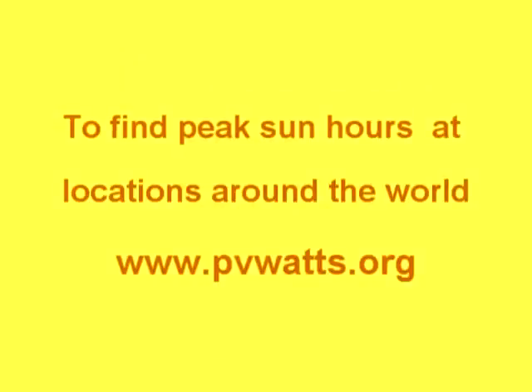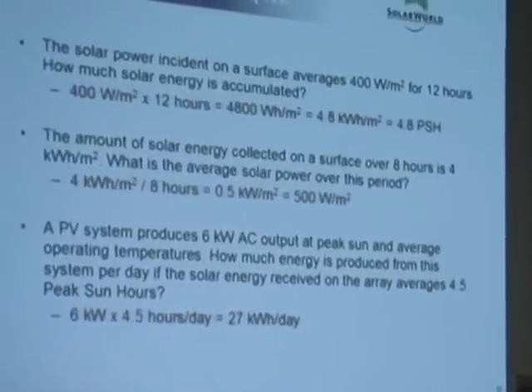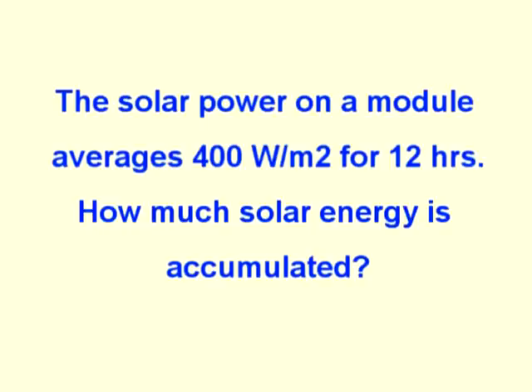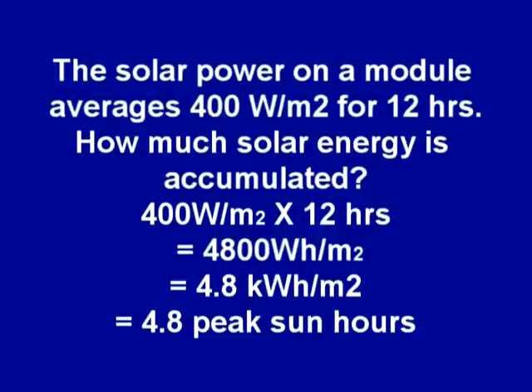You can find a link at www.pvwatts.org. Here are some sample calculations showing how to use the estimated amount of insolation to calculate the power output from a PV array. If the solar power on a module averages 400 watts per meter squared for twelve hours, multiply 400 watts per meter squared times twelve hours of sun, which equals 4800 watt hours per meter squared. Dividing by 1000 gives you 4.8 kilowatt hours per meter squared — and 4.8 is also the number of peak sun hours.